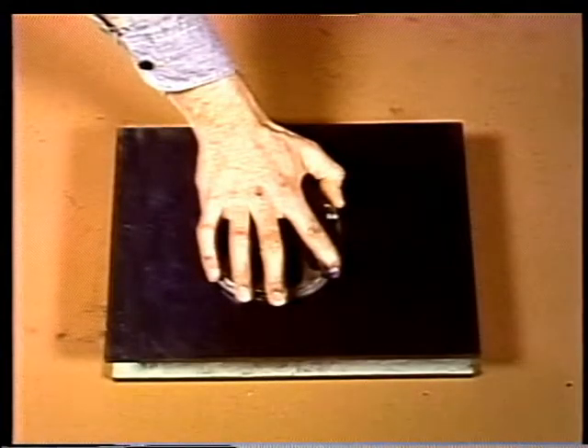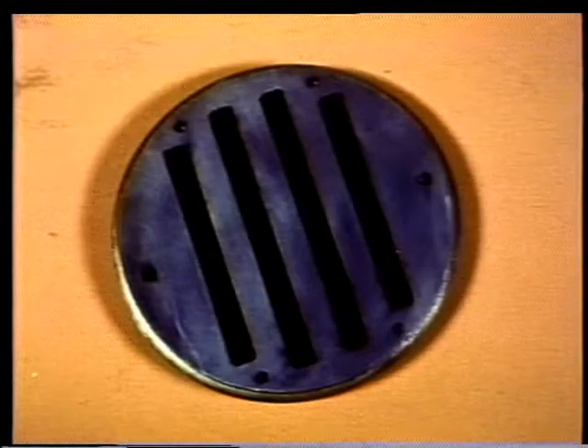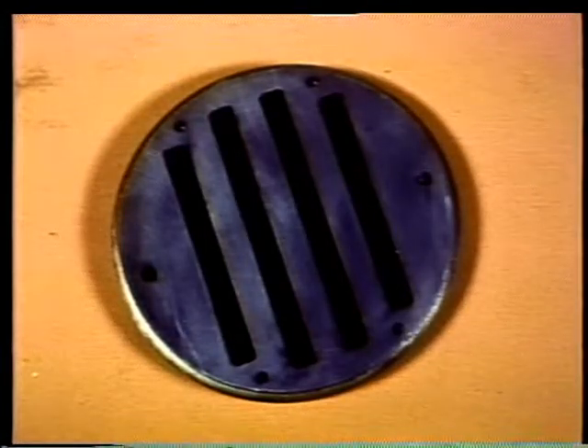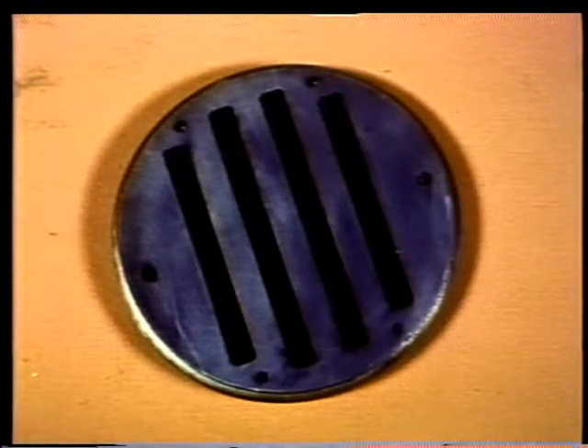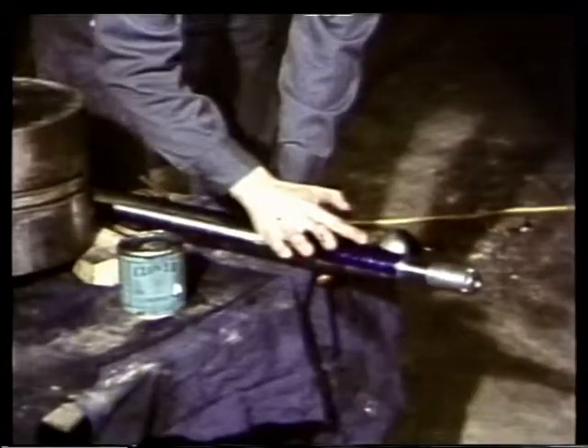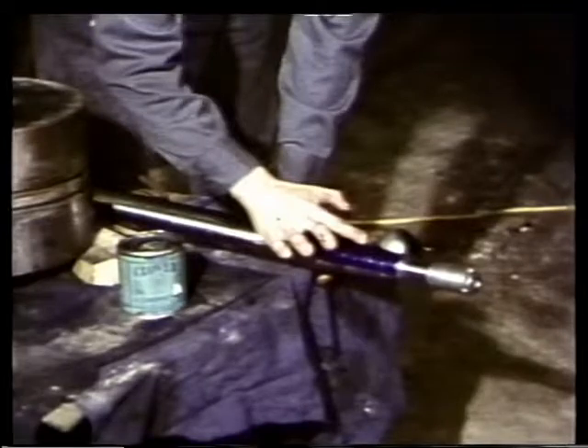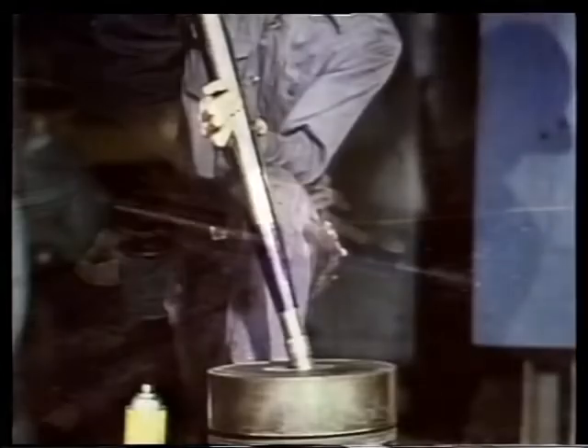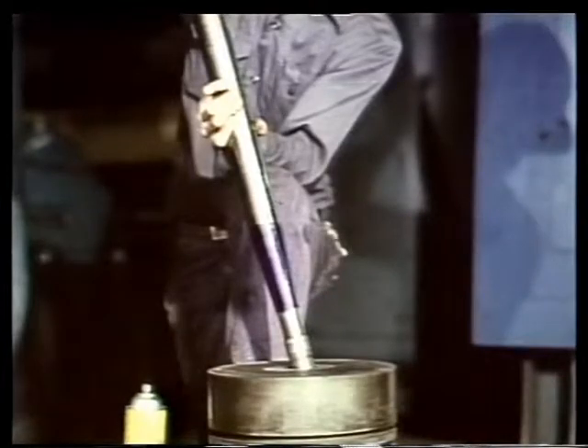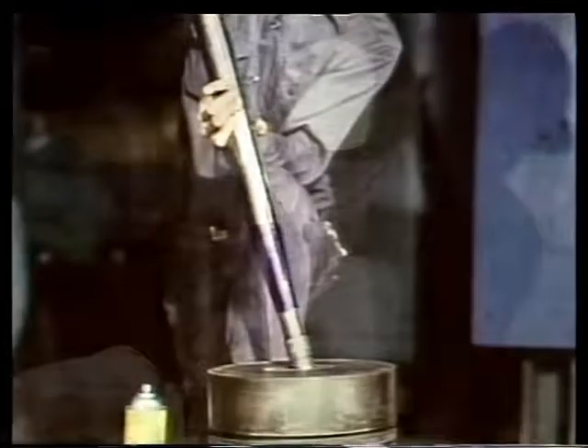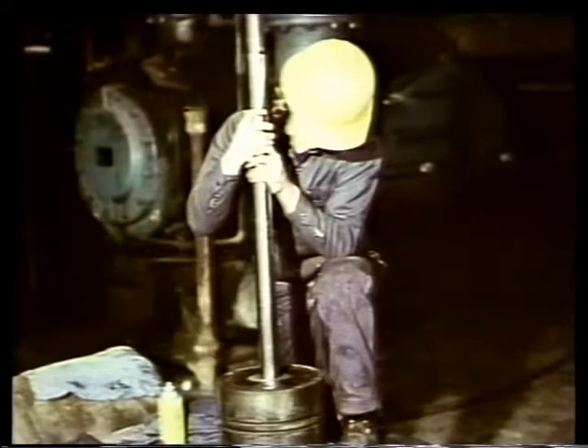Do you remember how bluing was used to check the results of lapping a valve seat? Well, you do the same thing to check the results of grinding in. Apply a thin layer of Prussian blue evenly around the entire piston rod and wipe off any excess. Then, insert the piston rod into the piston and rotate it a quarter of a turn.